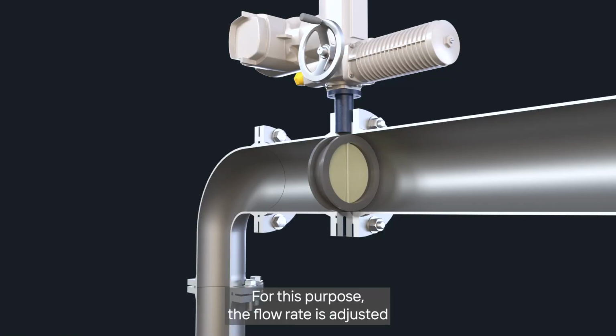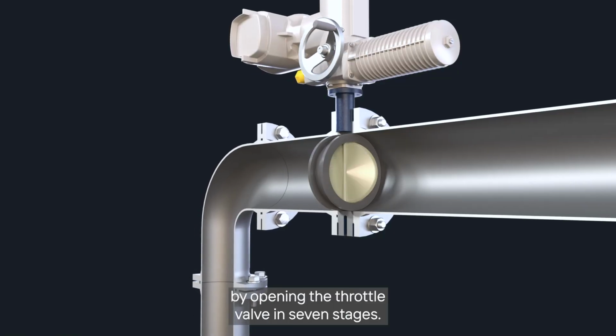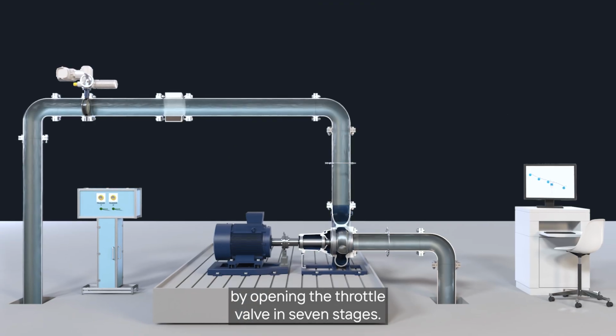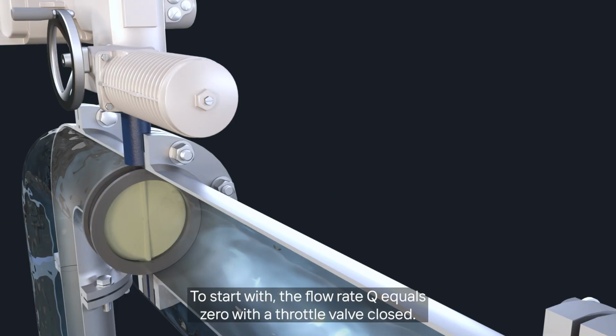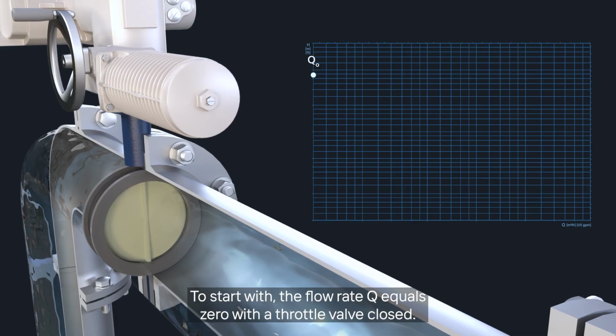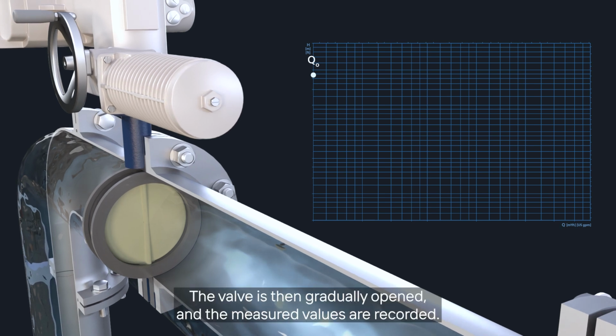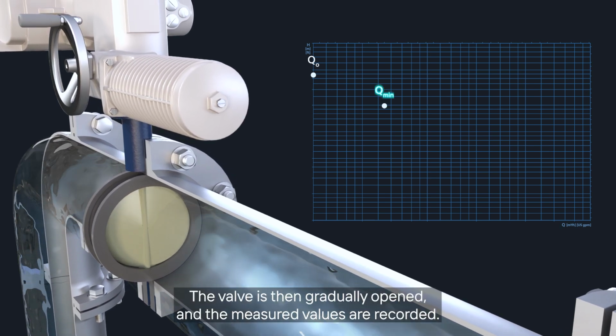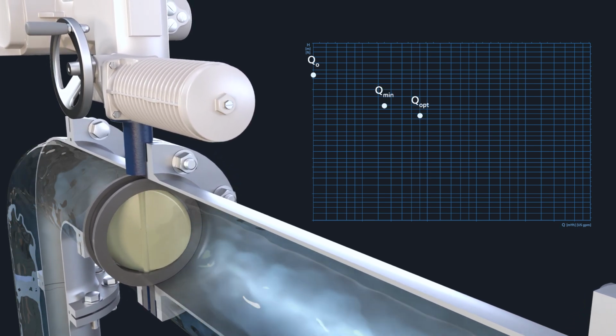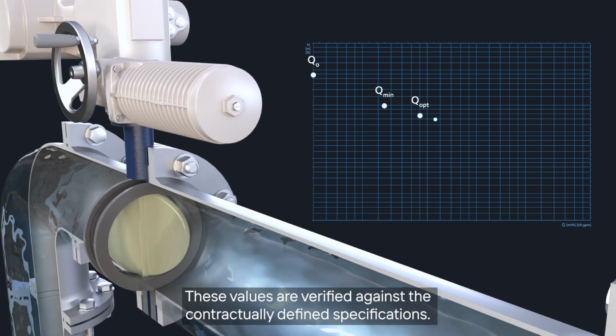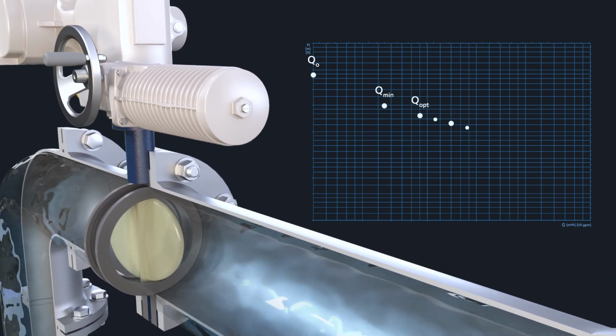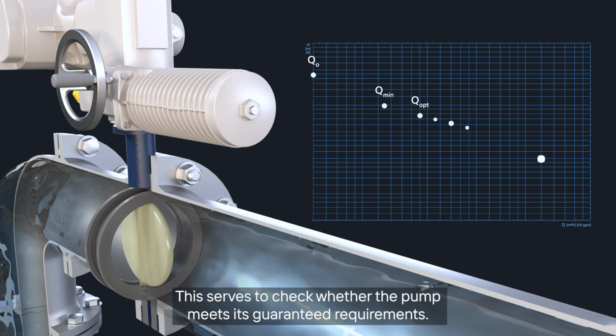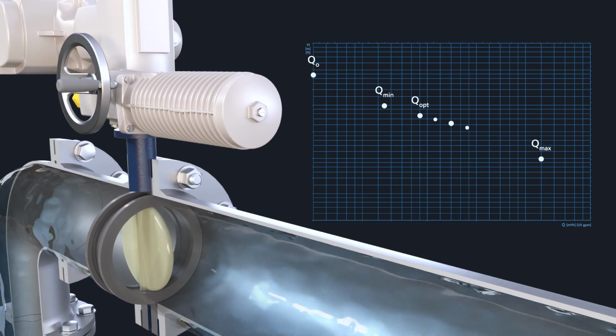For this purpose, the flow rate is adjusted by opening the throttle valve in 7 stages. To start with, the flow rate Q equals 0 with the throttle valve closed. The valve is then gradually opened and the measured values are recorded. These values are verified against the contractually defined specifications. This serves to check whether the pump meets its guaranteed requirements.